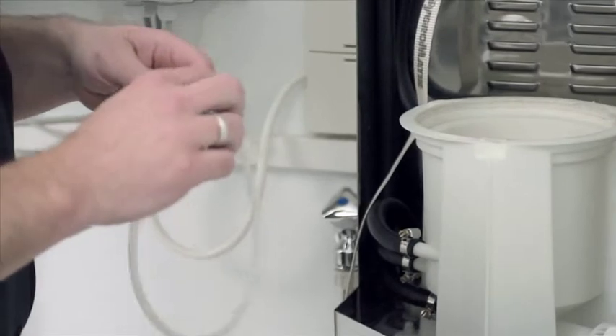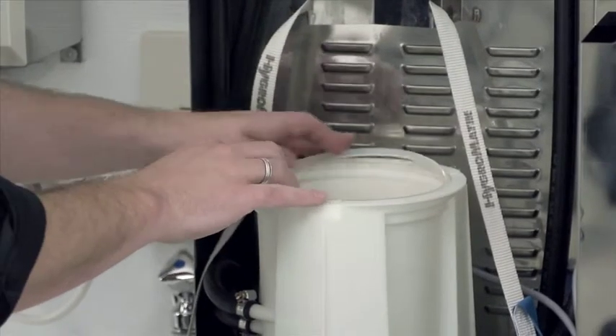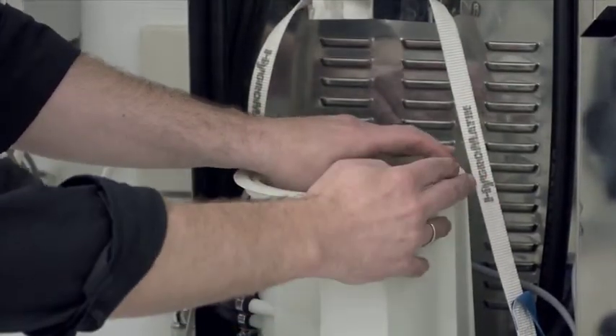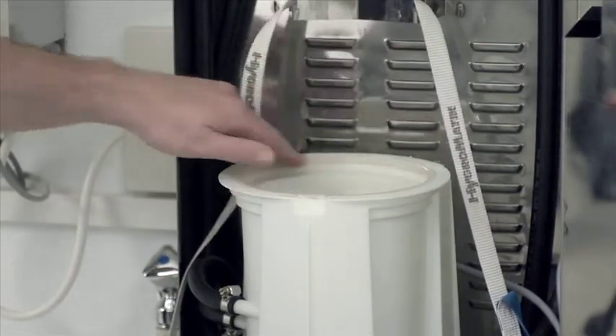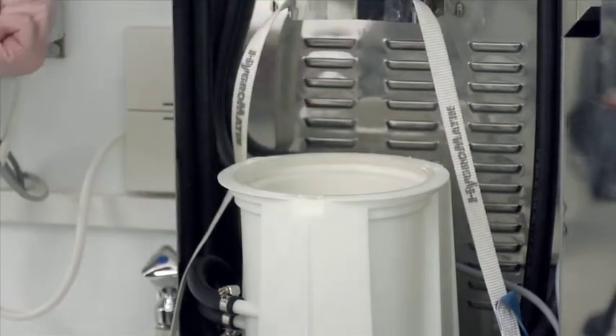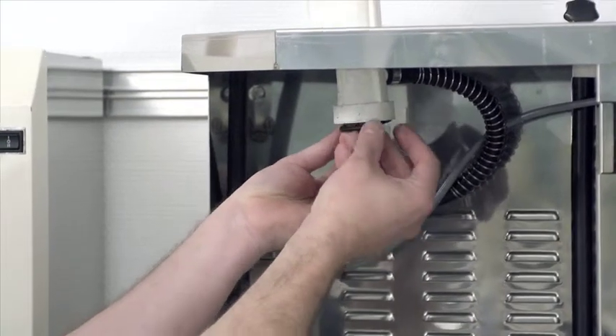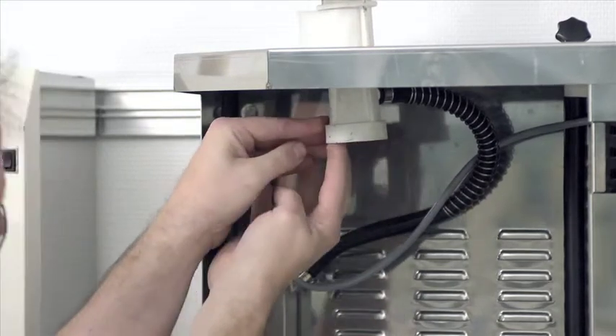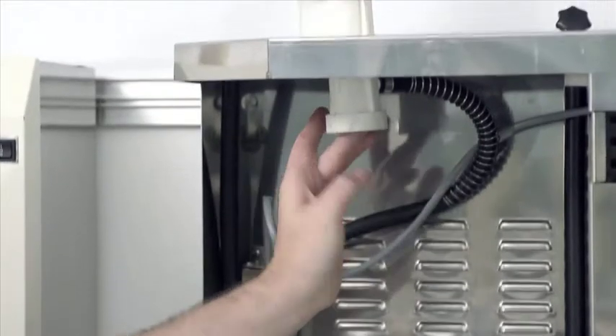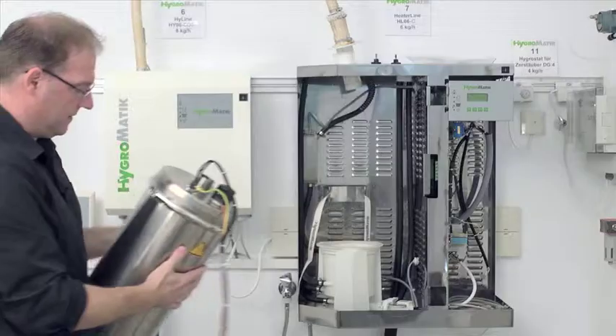Before we place the steam cylinder back I need to replace the O-rings. Down here the large white O-ring is placed, the silicon ring. You can see it has a bit oversized, that's important for it to seal correctly. That is seated properly, I'm going to wet it a bit so I can get the steam cylinder to fit in there nicely. We have replaced another O-ring, that was the one located up here in the steam hose adapter. I will place that one too now, wet it as well. There is always a little water down in there, I can take it from there and make it wet. And then I'll get the steam cylinder and place it back in.